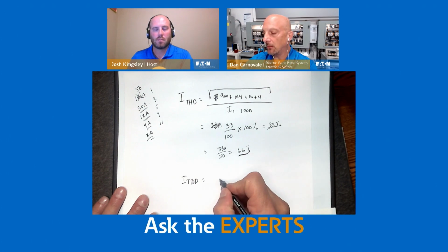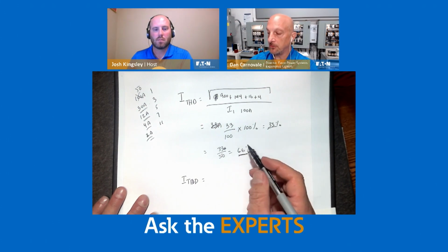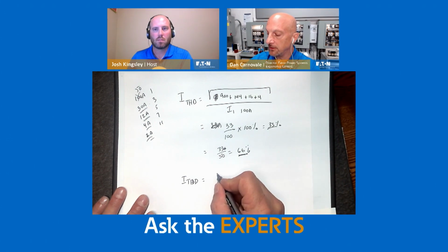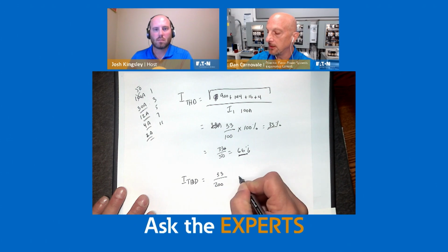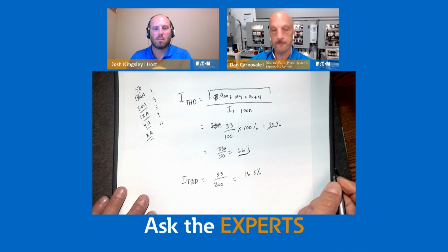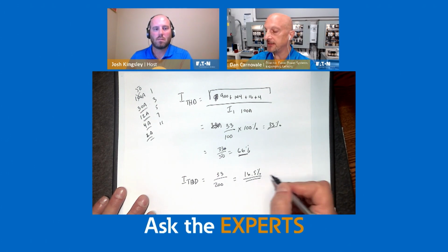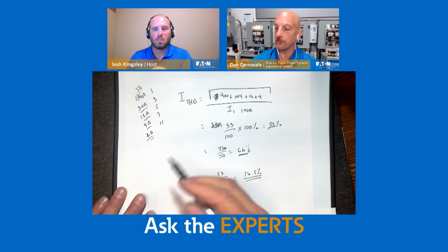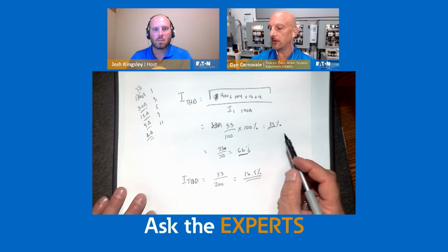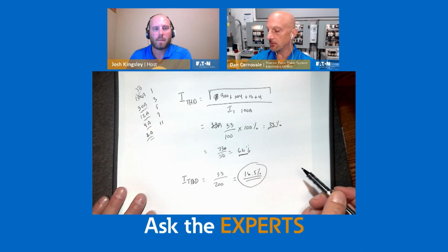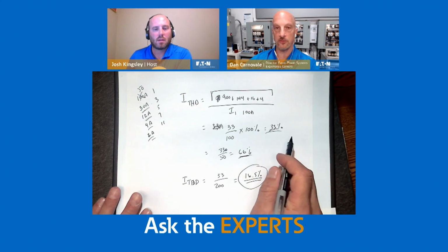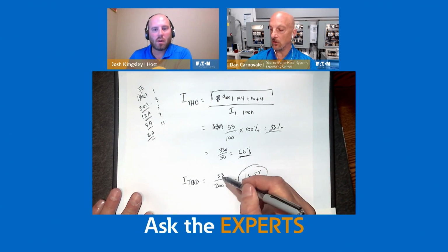So most of the time, let's say your maximum demand was 200 amps. Now your actual TDD would be 33 divided by 200, and that could be roughly 16.5% demand distortion, or TDD. Going through all that, what I mentioned earlier was the 519 standard says I could never go above 20%. This number would be within the 20%, and we would have to carefully look at that, see if it makes sense. This number is above, this number is above. But honestly, they're all okay. The same amount of harmonic current.